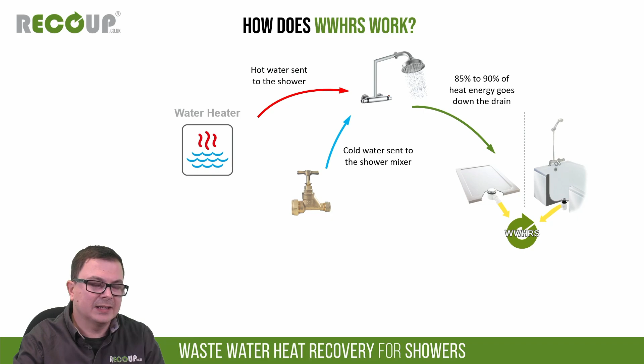So this is where we introduce wastewater heat recovery. It is a fairly simple heat exchanger technology. What we're doing here is recycling and reusing the heat energy from that wastewater. We're not mixing with it at all, we're not using the grey water itself, just interested in the heat energy from it. Now we take that through one of our heat exchangers. What you can see there is a little cut through of our vertical pipe hex. But they all work in a very similar way, where through the middle of our unit the wastewater flows, and then on the outside we have a cold main within our heat exchanger, which, through heat transfer through the length of our exchangers, recovers as much heat from that wastewater as possible, to give us a preheated feed coming out of the end of our units.